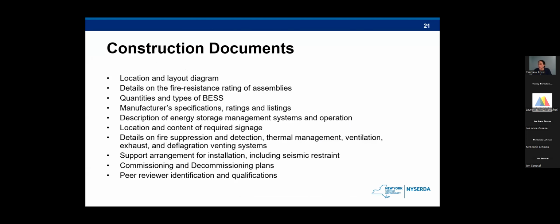So here are all the construction documents that are required to be submitted along with the permit application required by the Uniform Code. So we will go through the code in more depth and more detail on many of these requirements and how they'll be met. But basically when an applicant provides their permit, they need to make sure they include the location and layout diagram, details on the fire resistance rating of assemblies, the quantities and types of battery energy storage, any manufacturer specs, ratings, and listings, the description of the battery management system, the location and content of the required signage.